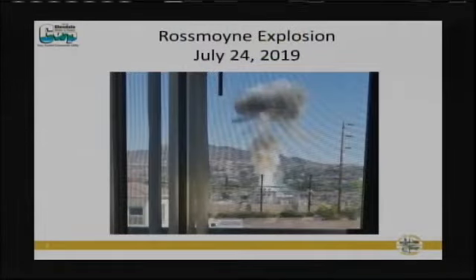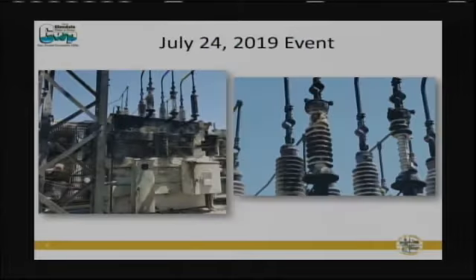This was the actual photo of the explosion from a distance that was taken by one of our residents and sent to us. So when we use the term explosion, it's pretty accurate when you look at the situation here. This is the damage that it caused. The lid of that auxiliary transformer, that small cylinder there, went up into this bank of resistors and damaged them. These are all porcelain devices, and it literally ruined all of these. It broke most of them, as you can see, or they have sustained some damage, some complete damage. You see the burns to the device, and you see the burns to the transformer itself.